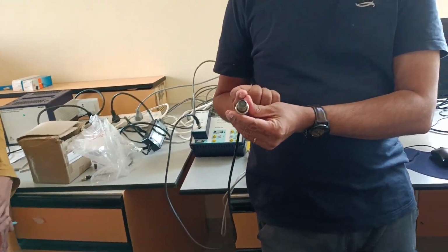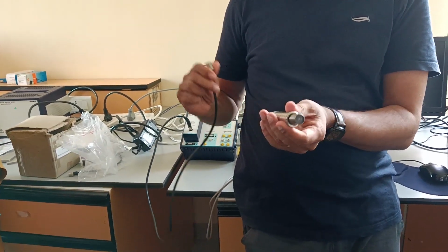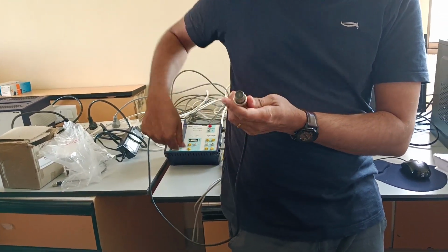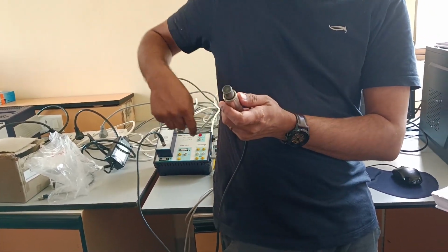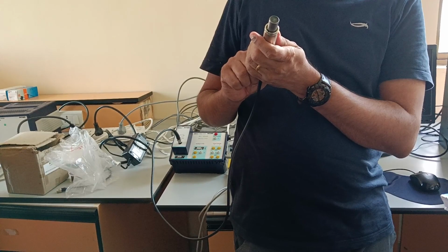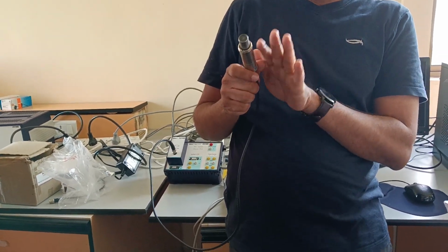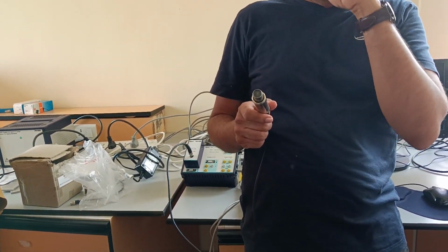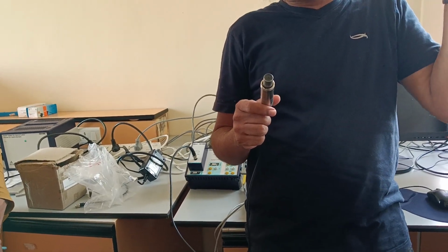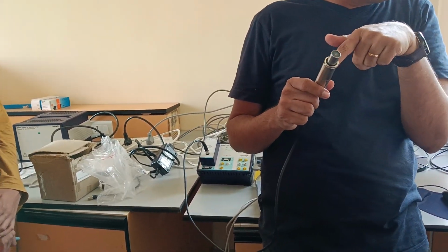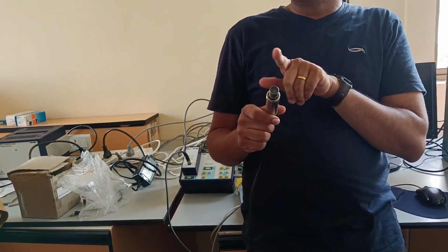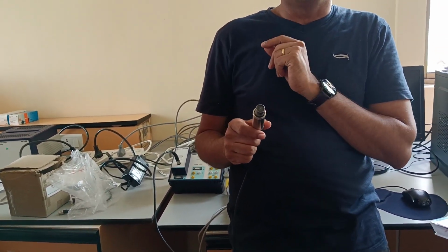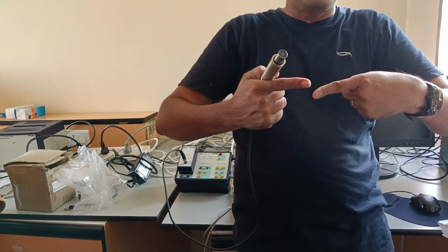a tungsten needle, and a high voltage, 600 volts, is applied through this box. Don't worry, you will not be electrocuted. Its current capacity is extremely low. That voltage is applied to this needle, and you have low pressure inert gas. What happens is whenever high energy radiation interacts with the wall, it produces some charged particles, and the needle is given a very high positive voltage, 600 volts. So the electrons rush to the center of the needle.